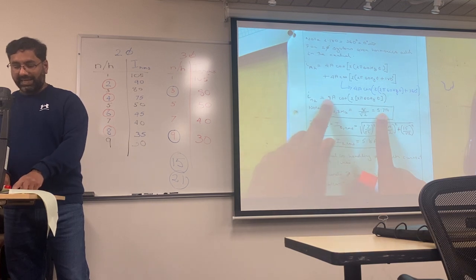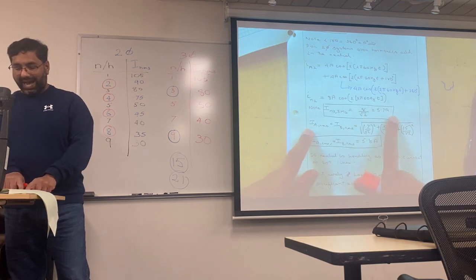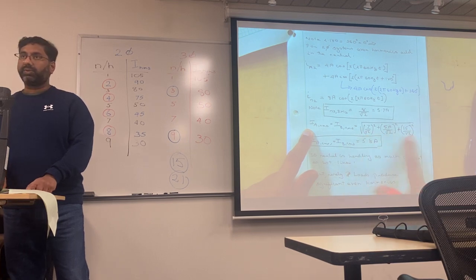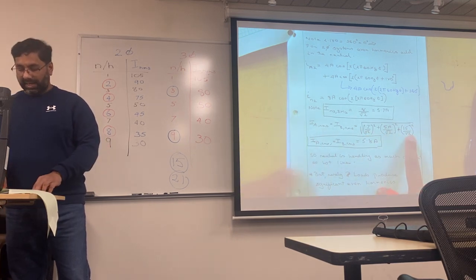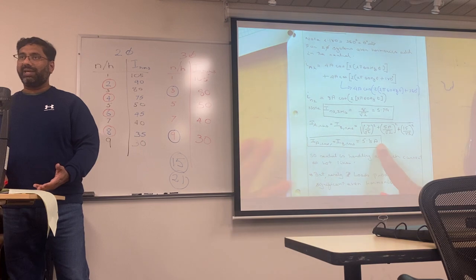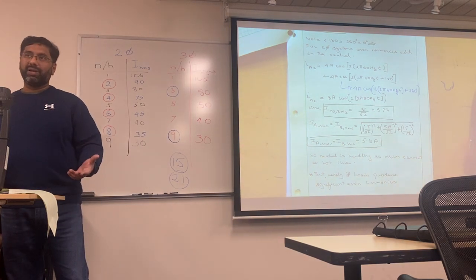So in the neutral, I only have an even current. I take the V max of this, divide by root 2, I get 5.7 amps. And the line current is what I did here: IA1 RMS, IB1 RMS, so it was 7, 5, and 1.5, and I did root 2 to make it into RMS. And what did I end up with? 5.8 amps. In other words, the neutral and the RMS effectively are almost the same current.